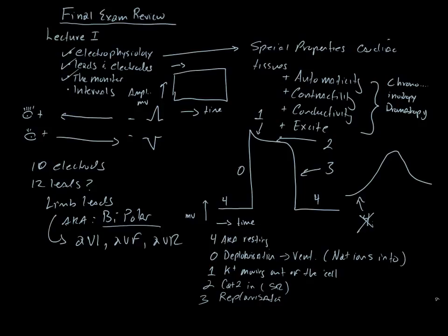The standard paper speed is 25 millimeters per second. You guys okay with that?